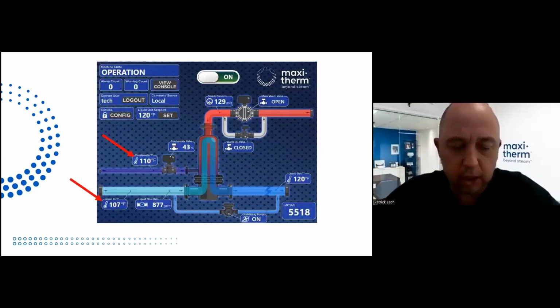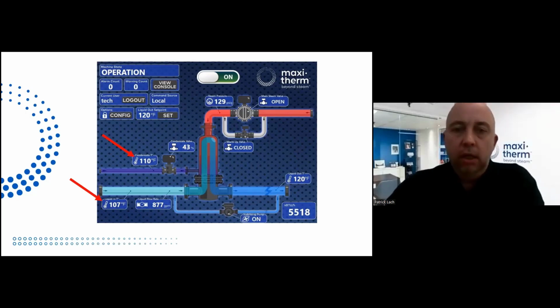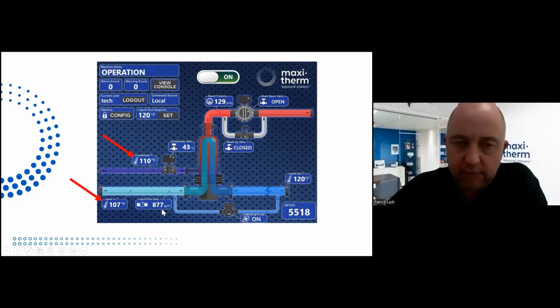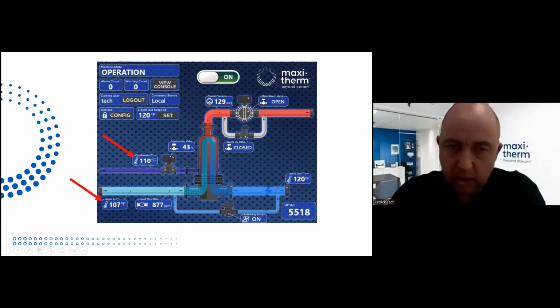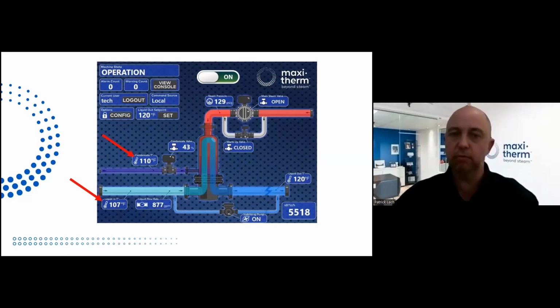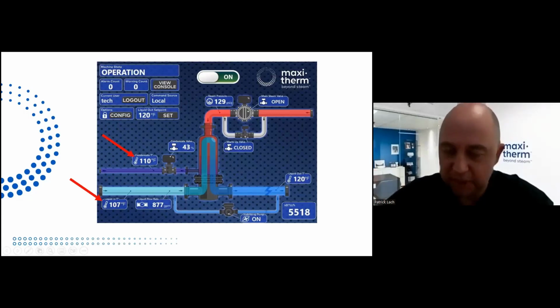Now, this is a screenshot we took at Liberty Place building, downtown Philadelphia, okay? They're dumping condensate to drain. We're using 129 PSI steam. You have, by the way, on the touch screen, the BTU monitoring and the flow rate at the actual flow rate. So we're having a 5.5 million BTU load right here. Look at the temperature return, 107 Fahrenheit. Look at the temperature discharge of the condensate. A 3 Fahrenheit difference with the temperature return, because we're not at full load here. Full load will be, like I said, 130, depending on your set point and your temperature return, basically. There are other reasons, but yeah.